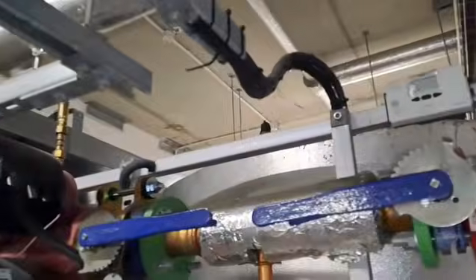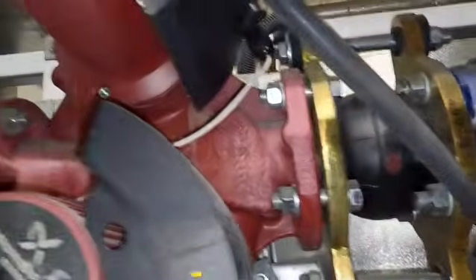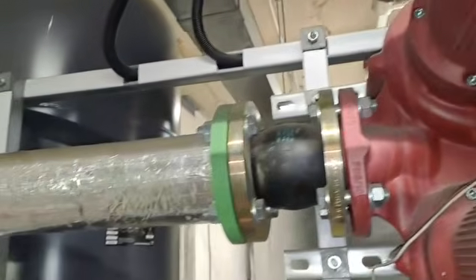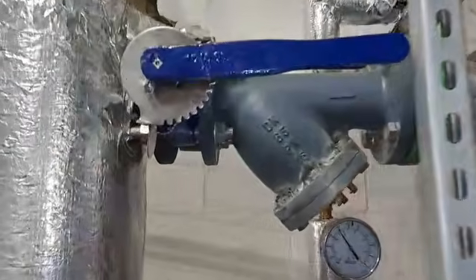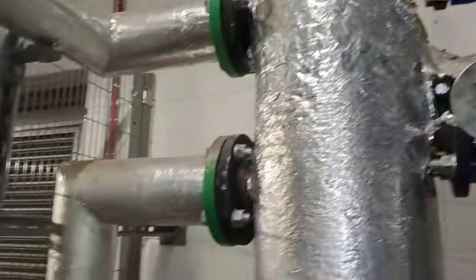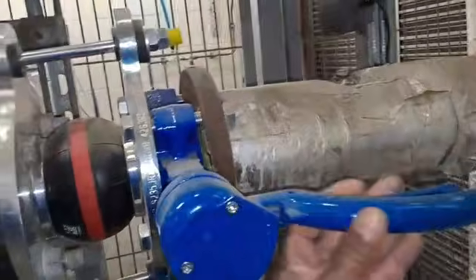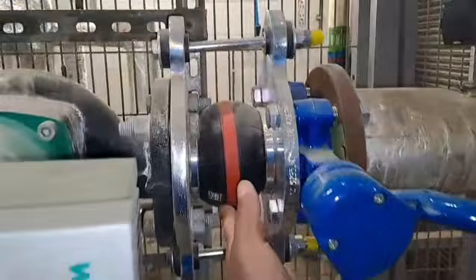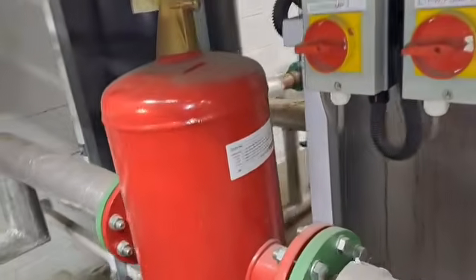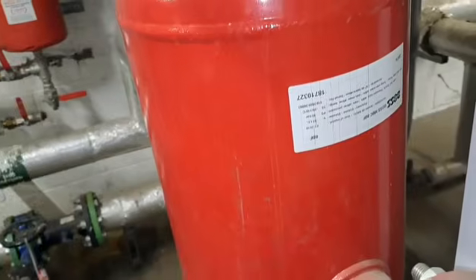Then we got a meter and loads of valves, and then bellows, a pump which is obviously going that way, a Grundfos Magna, and more bellows, strainer, and more butterfly valves. Butterfly valve, a nice fancy looking sleek butterfly valve. Bellows, a Wilo pump, strainer again. There's loads of strainers in here, which is good, and it goes over there. And then a dirt and air separator, a Boss NBC.